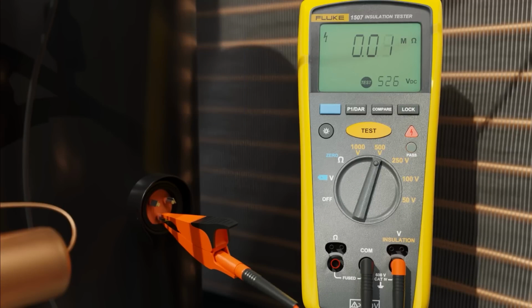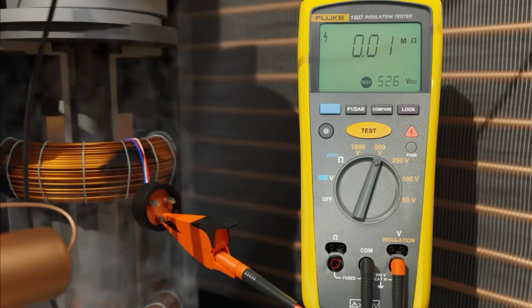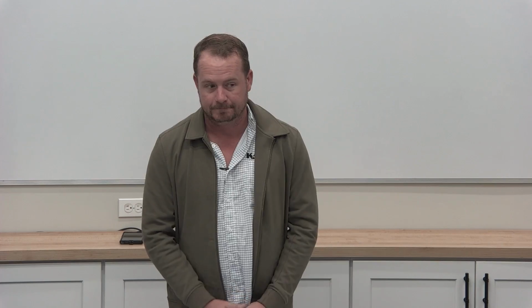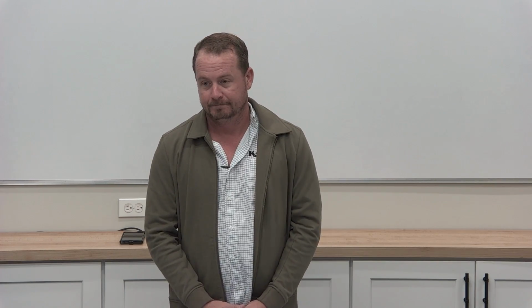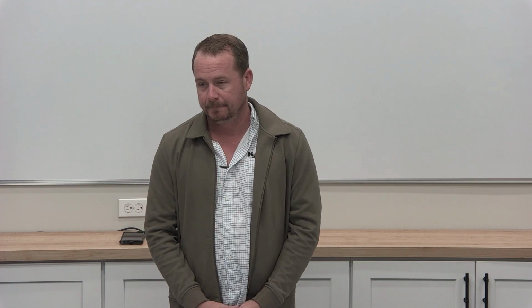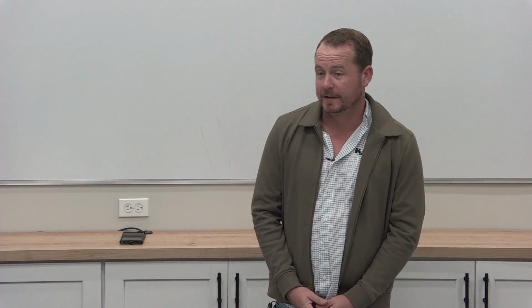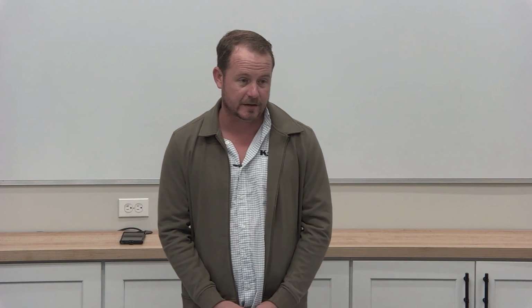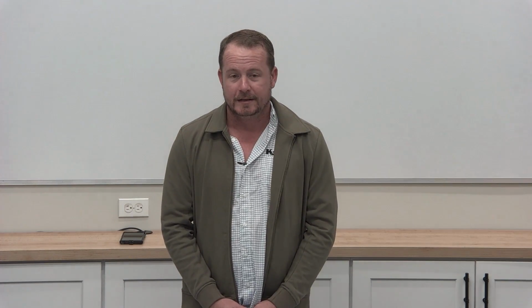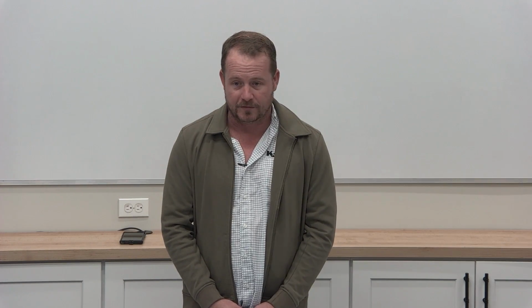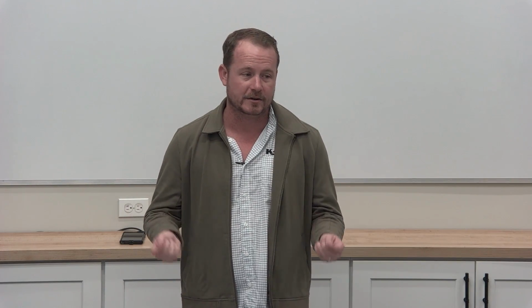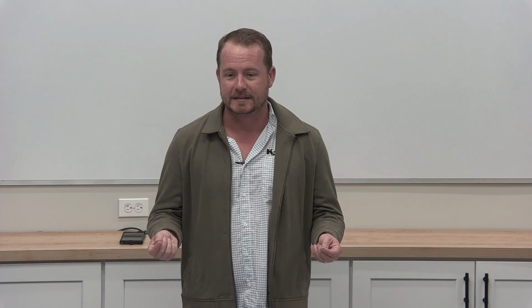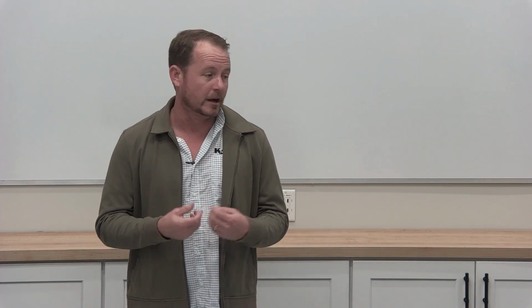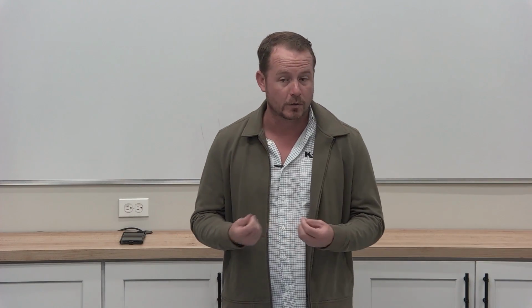Now, is that still a fail-safe way of doing a safety check? No. Why? You could have issues with your meter lead connections, battery level. Could be that you don't have a good enough ground. So if it's ungrounded, then you're not necessarily going to see a measurement. Nothing is going to be completely perfect, but you want to go through a standard set of tests. One of the easiest things to do is to use a non-contact voltage detector, one that is working.